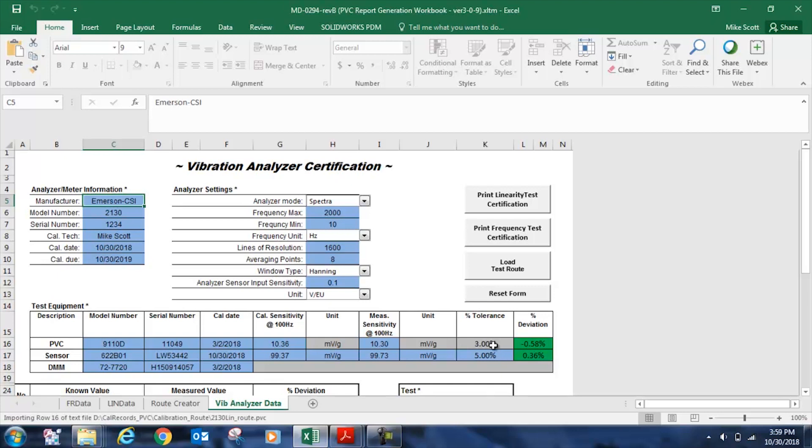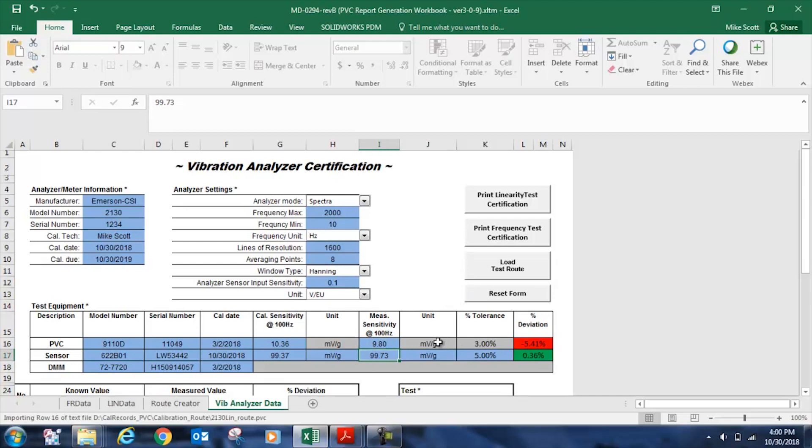If the deviation were greater than the accuracy tolerance of the shaker, which is 3%, this cell would be red. So if we measured it to be 9.8, for example, millivolts per G, the cell would turn red, and it would let me know that I shouldn't be using this calibrator to test my 2130.